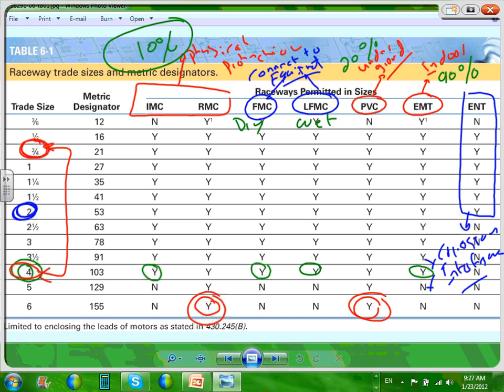The same thing with this. This one is ENT, and you can bust it if you push too hard on it. This is non-metallic tubing. But most of the time they use them in short parts, 10, maybe 15, 20 feet, and then they go to a junction box and keep moving with them. You're not going to pull 100 feet of this and pull the conductor inside it. Any question, guys, about this? So that's what I thought to start with.